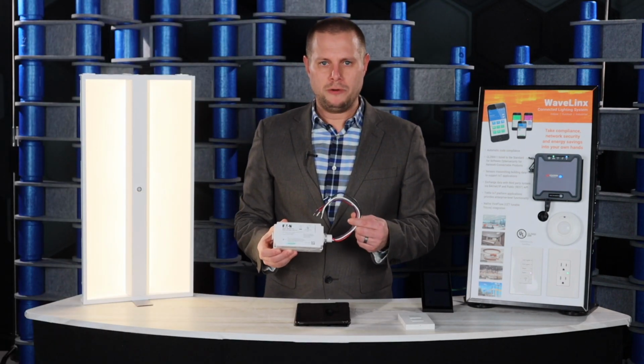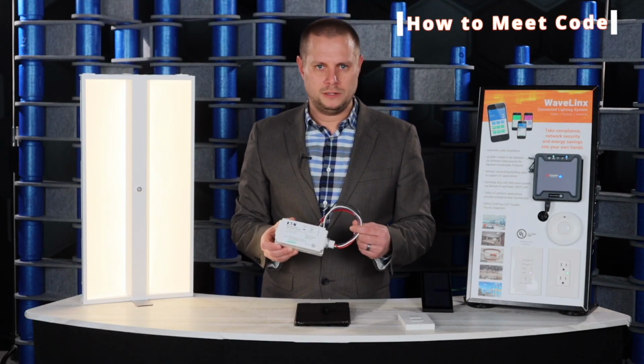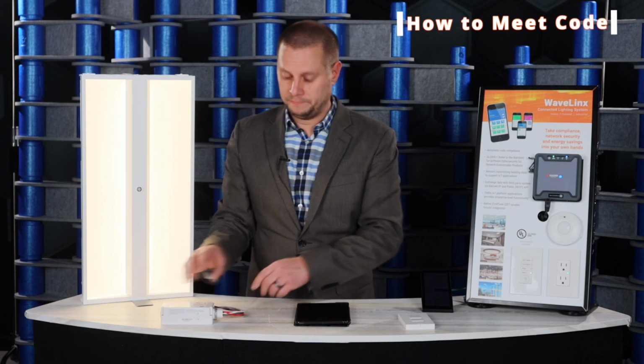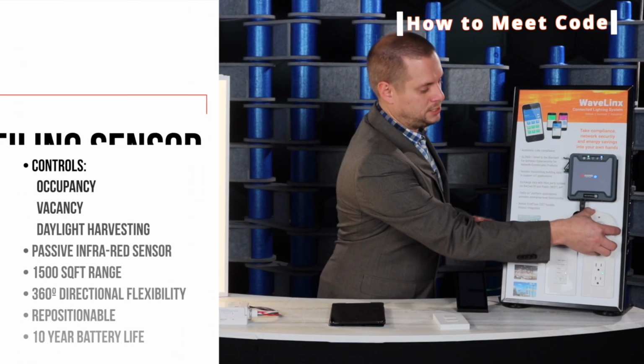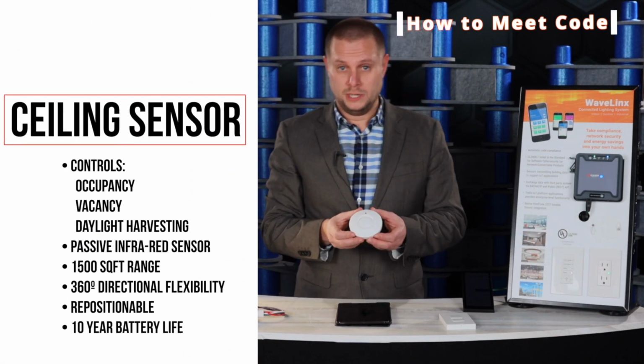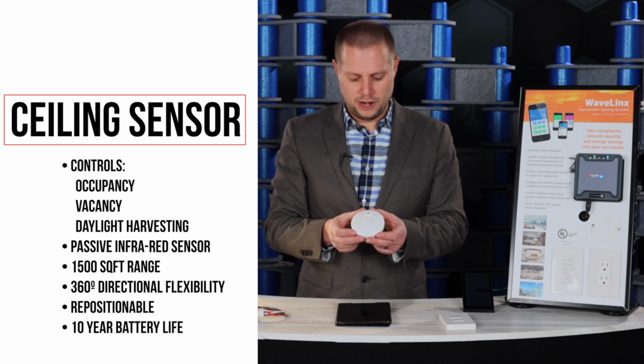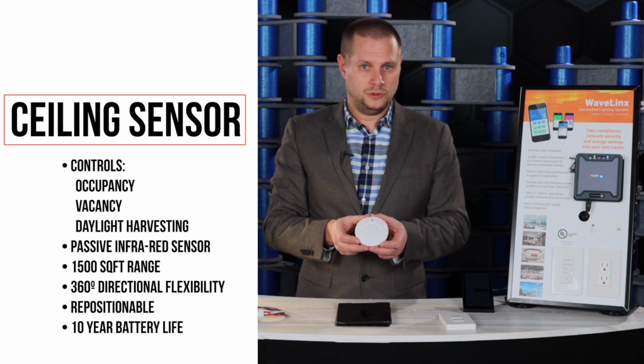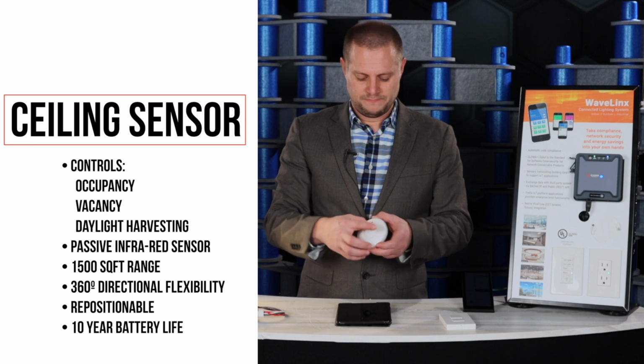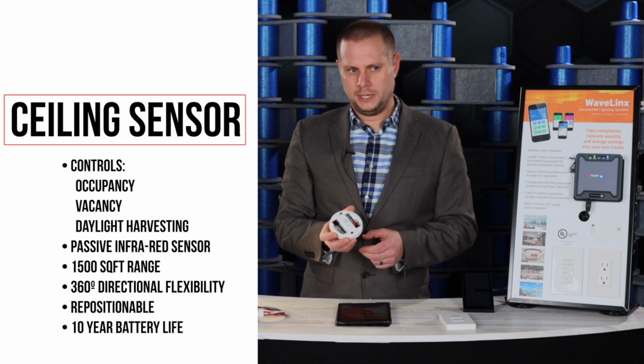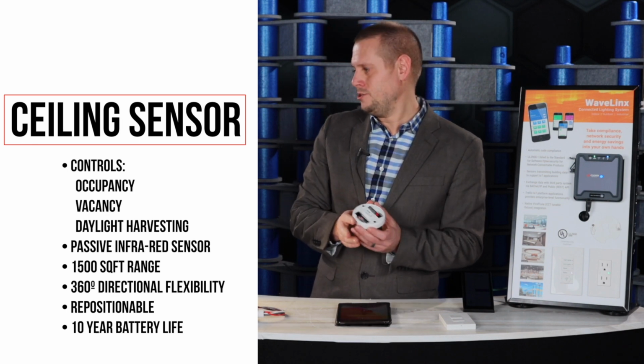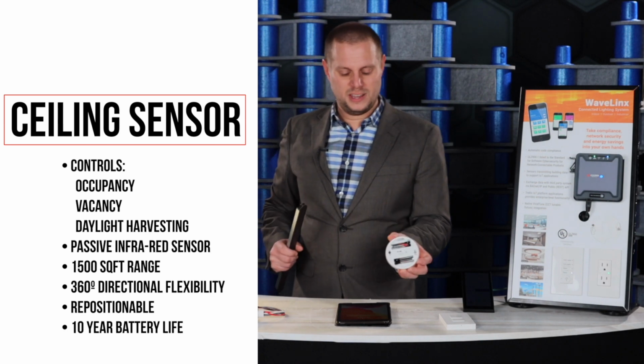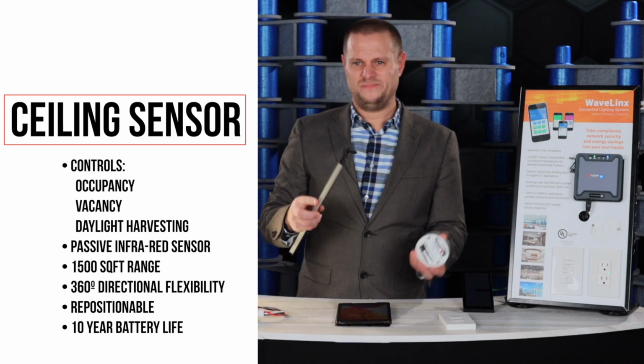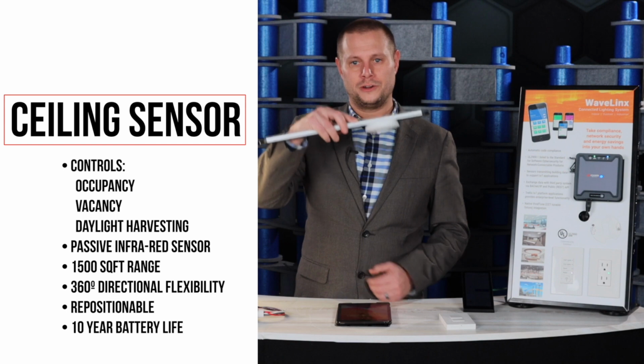So if we're using this power pack solution, how do we get daylight and occupancy to meet code? Good news—there's a sensor that does occupancy, vacancy, and daylight harvesting. You can use it for small areas or large areas. It's powered by a pair of AAs, warranted for 10 years, and has a magnet on it, so it slaps right onto the grid.